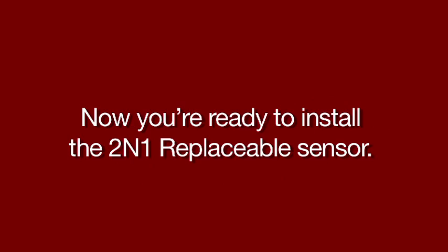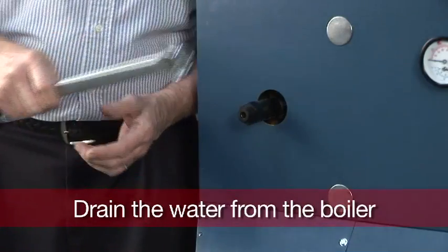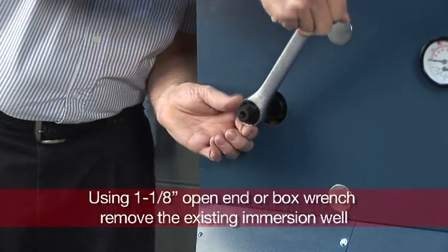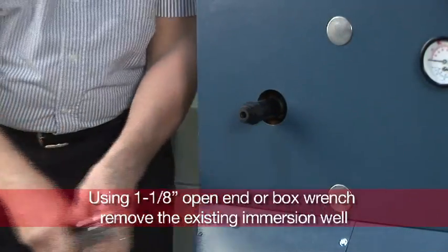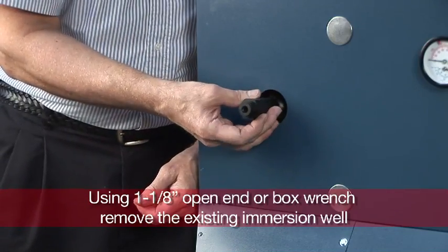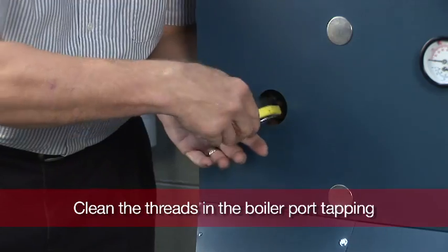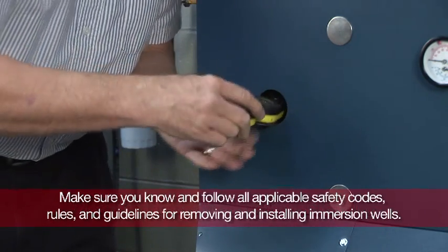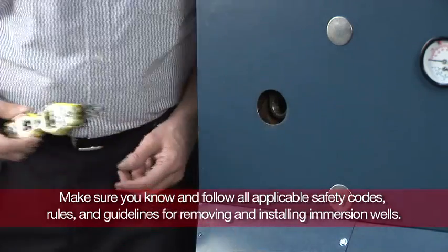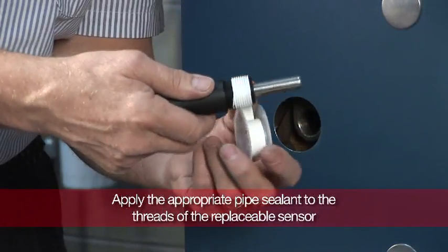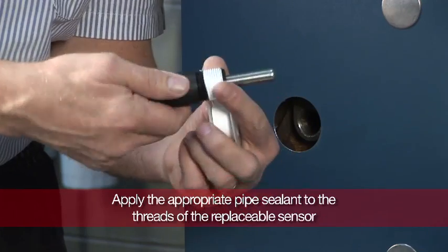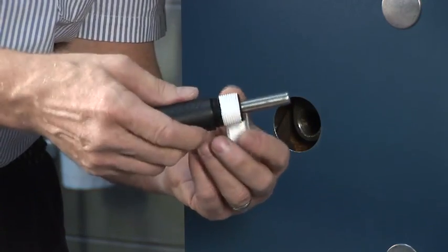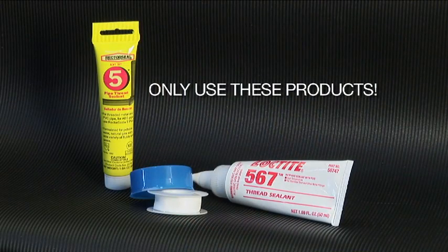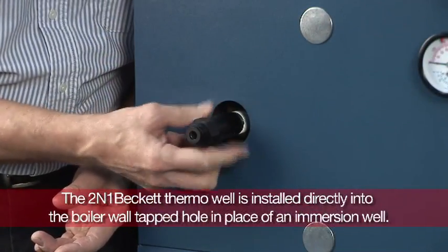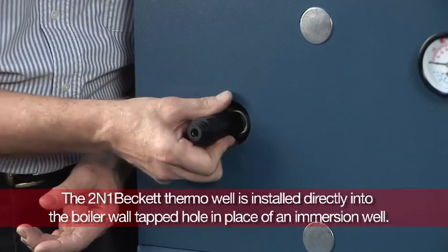Now you're ready to install the 2-in-1 replaceable sensor. Begin by draining the water from the boiler. Next, using a 1 1/8-inch open end or box wrench, remove the existing immersion well and clean the threads in the boiler port tapping. Make sure you know and follow all applicable safety codes, rules, and guidelines for removing and installing immersion wells. Now apply the appropriate pipe sealant to the threads of the replaceable sensor. As mentioned earlier, only use the sealants that Beckett recommends. This also includes Teflon tape or Rectorseal No. 5 soft set.